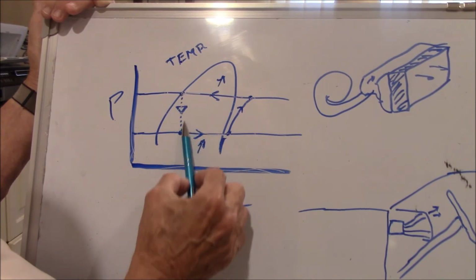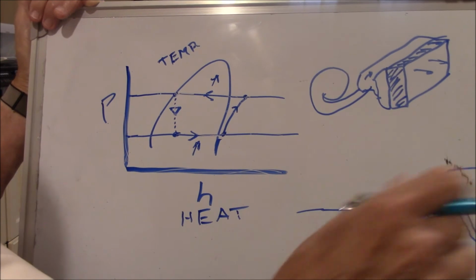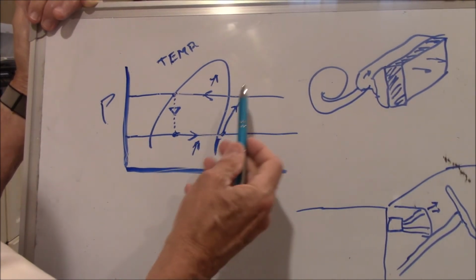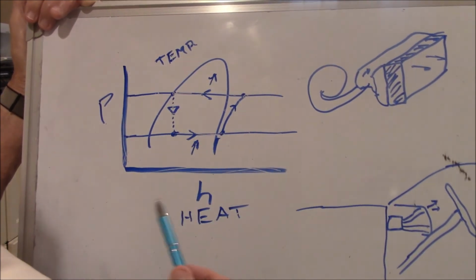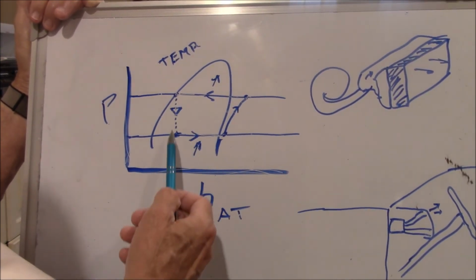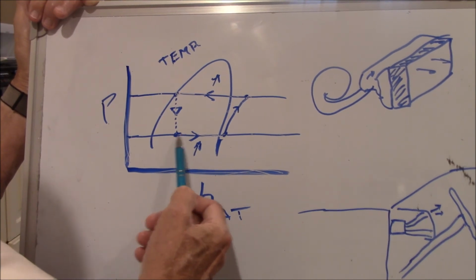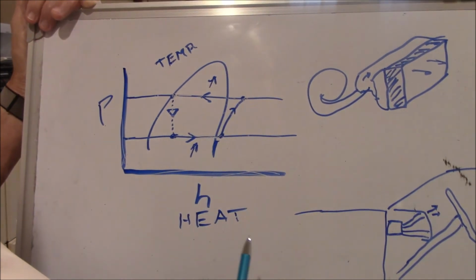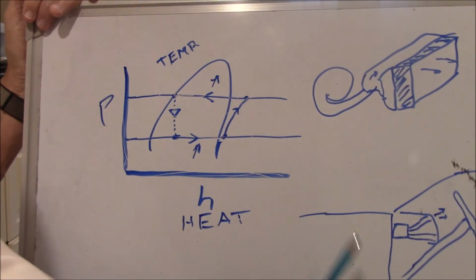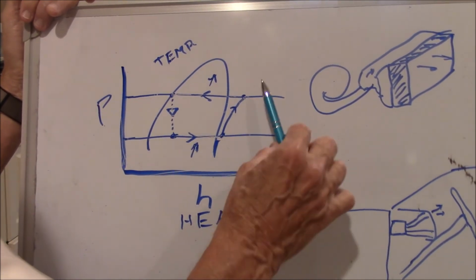When your compressor is running outside, it's pumping up, you're rejecting the heat. When you feel the top of that condensing unit, that's what the outside unit's called, a condensing unit, because it's taking gas and condensing it down to a liquid. And the evaporator inside is called an evaporator because it's taking the liquid and evaporating it into a gas. But it's a low side and a high side. And that's the basic classic description of a refrigeration system.